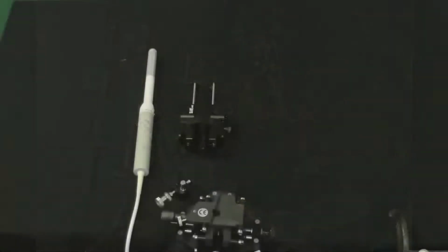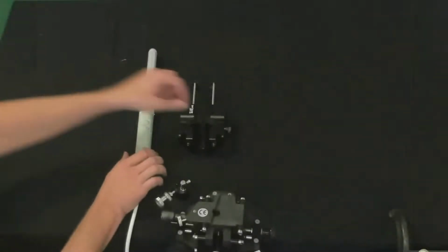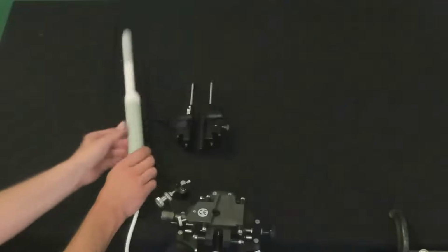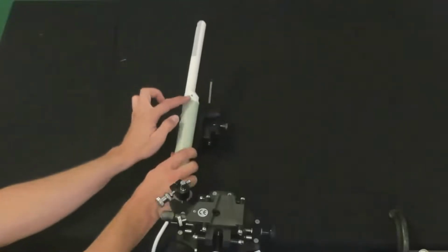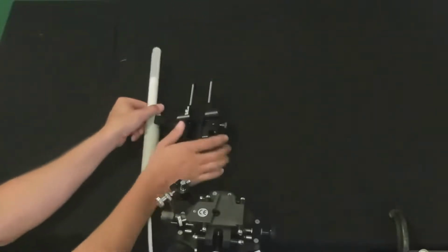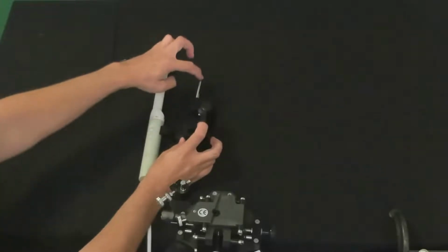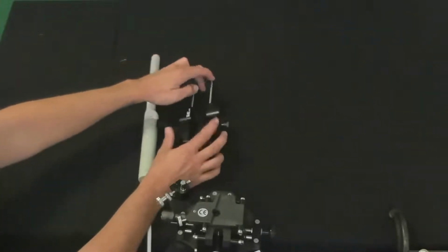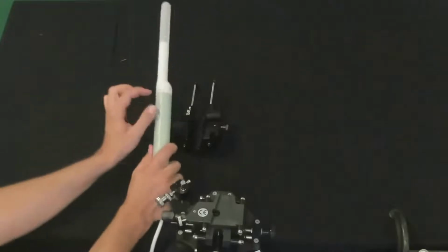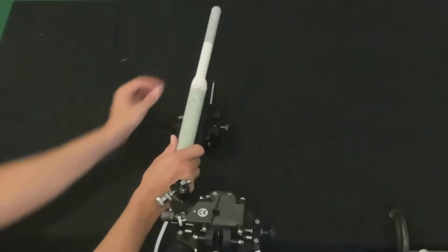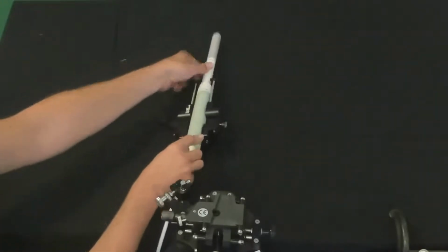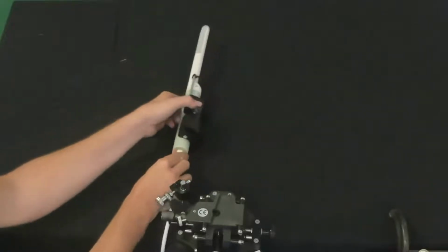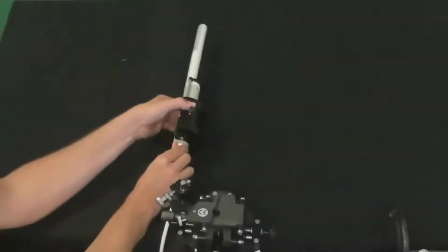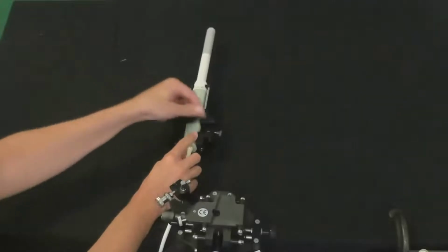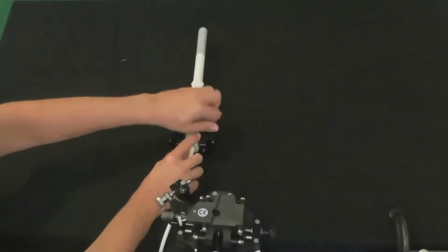The first thing we need to do is fit the transducer into the cradle. So we open the clamp, then locate the pin on the transducer, then locate the notch on the cradle. Then we slide the transducer with the pin into the notch on the cradle so that it stays in place during the procedure. Then we close the clamp and tighten the screw.